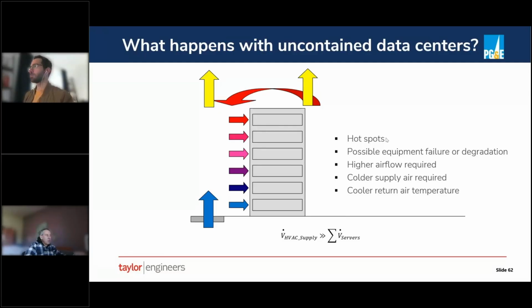And so it was common to have hot spots and failures. You needed to blow a lot of air. The supply from the HVAC needed to be much, much greater than the airflow that the servers were pulling. Cold supply air, not uncommon in early generations of data centers, was supplied at a 50, 55 degree supply air temperature, basically keeping the whole space almost like a meat locker. The original CRAC units were designed to operate typically at a 70 to 73 degree return temperature, which meant the whole space was much colder.